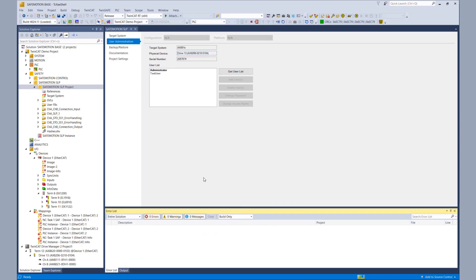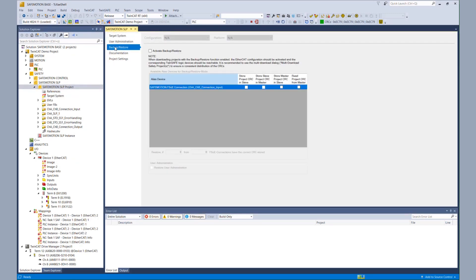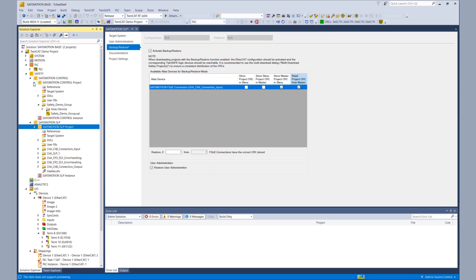Now we can start the configuration of the backup and restore. We go to the target system property page of the AX8000, then to the tab backup and restore. Here we activate the backup and restore, and now we configure the dependence between the EL6910 and the AX8000. In our case, the AX8000 is the slave, so we want to store the master project CRC in the slave and read the project CRC from our master. We also want to restore the user administration. That was all for the AX8000.